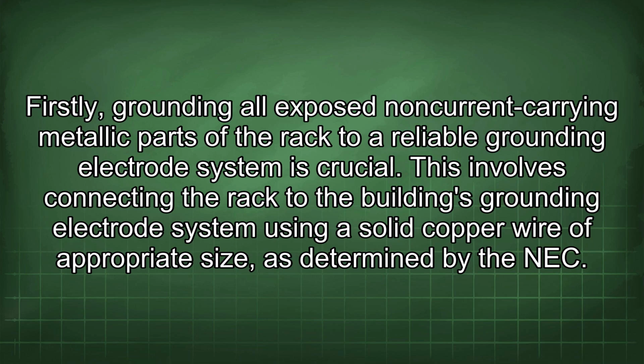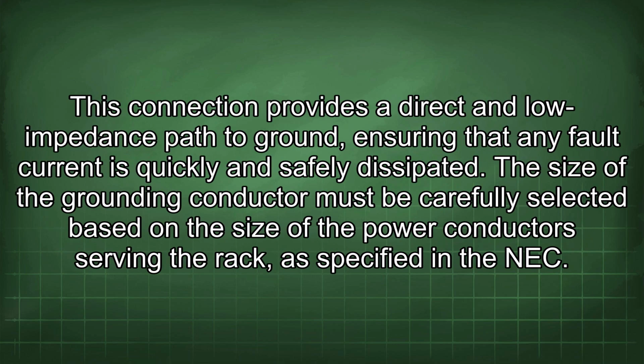Firstly, grounding all exposed non-current carrying metallic parts of the rack to a reliable grounding electrode system is crucial. This involves connecting the rack to the building's grounding electrode system using a solid copper wire of appropriate size, as determined by the NEC. This connection provides a direct and low impedance path to ground, ensuring that any fault current is quickly and safely dissipated. The size of the grounding conductor must be carefully selected based on the size of the power conductors serving the rack, as specified in the NEC.